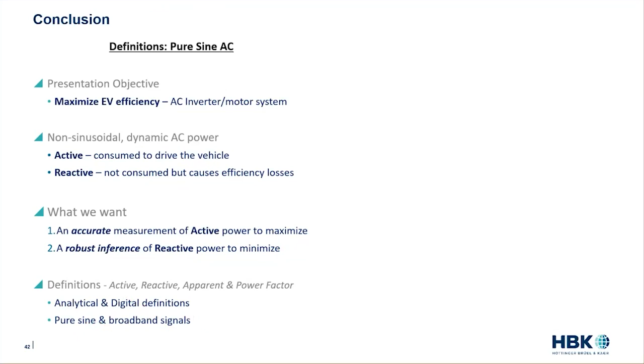So in this case, we used a time domain approach, which is the windowed statistical method. This is the same one that eDrive uses internally. So it's a pure sine method, but for EVs, that's not a problem. We can put in a low-pass filter to isolate the fundamental from the switching harmonics, and then it works brilliantly well. And the benefit is we can go right down to the half-cycle resolution. So it's really tight resolution. That makes it ideal for the Worldwide Harmonized Light Vehicle Test Procedure.